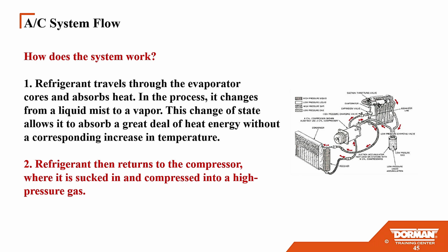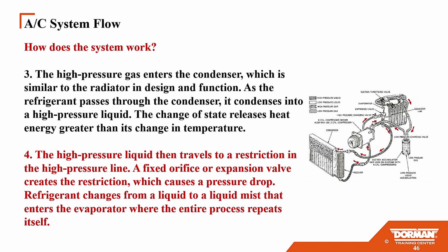Okay. And then refrigerant returns to the compressor, it's sucked in and compressed into a high pressure gas. High pressure gas enters the condenser, which is similar to the radiator design. So as the refrigerant passes through the condenser, it condenses into a high pressure liquid. Change of state, again I mentioned right from the very first slide, change of state, releases heat energy greater than its change in temperature. High pressure liquid then travels through a high pressure line to a restriction. You got a fixed orifice or expansion valve that creates a restriction, and it's going to cause a pressure drop. Refrigerant changes from a liquid to a liquid mist, enters the evaporator, where the entire process starts repeating all over again.